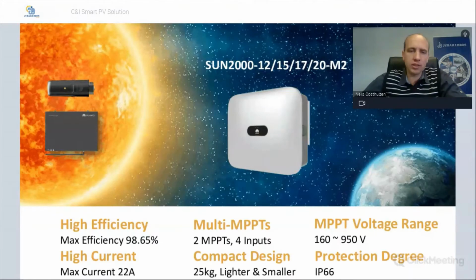On this next slide, it's just a brief explanation of the 12 to 20 KTL M2 range. M2 meaning it's the second generation of the inverter, or the second time that the inverter has been redesigned, tweaked or improved. So the 12 to 20 KTL range has got a 98.65% efficiency, 22 amps per MPPT, 2 MPPTs. So we've got a compact design, it's 25 kg and lighter, so one person can handle it. And then the voltage range is between 160 and 950 volts on the MPPT.